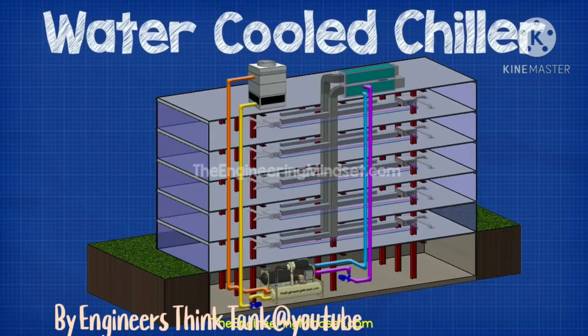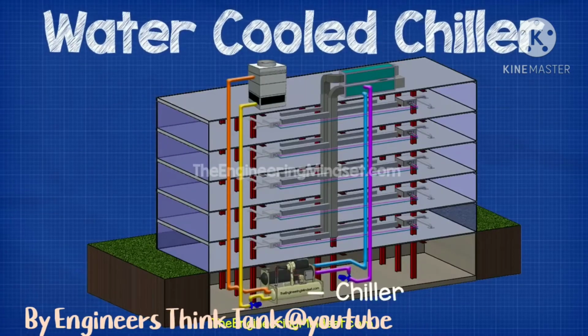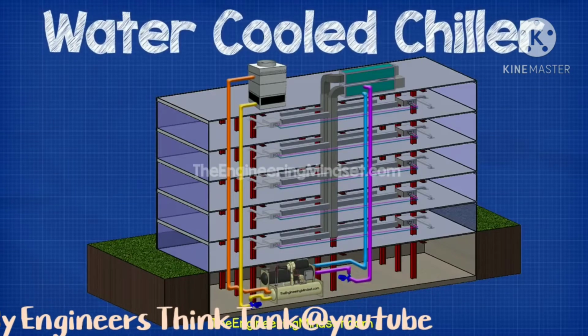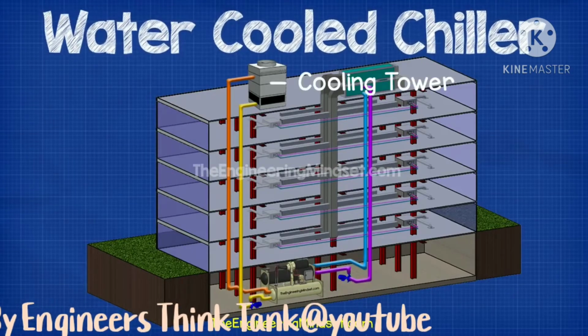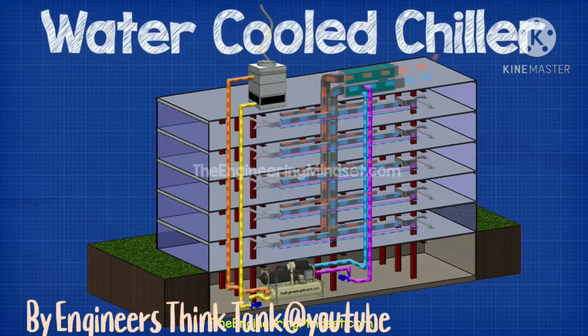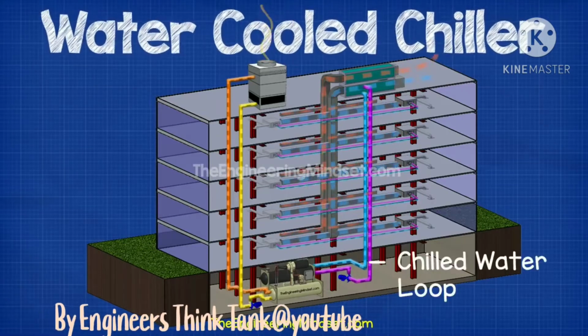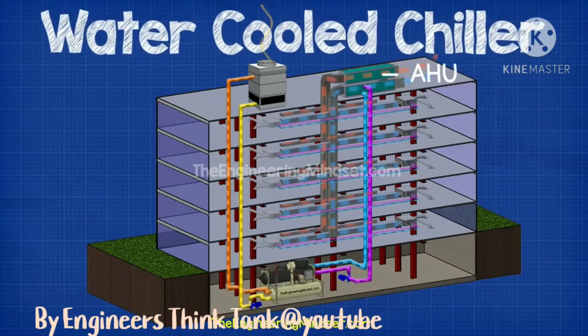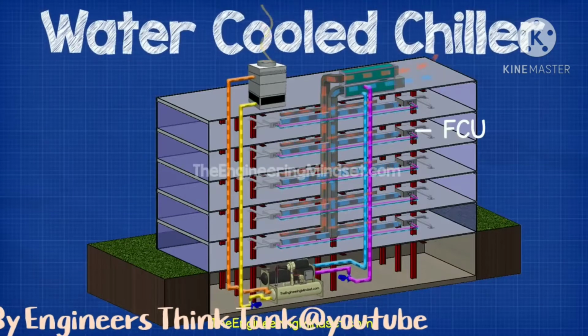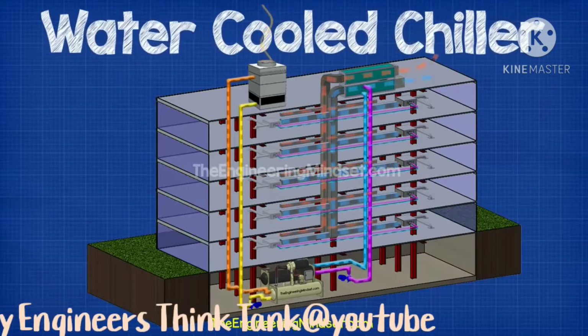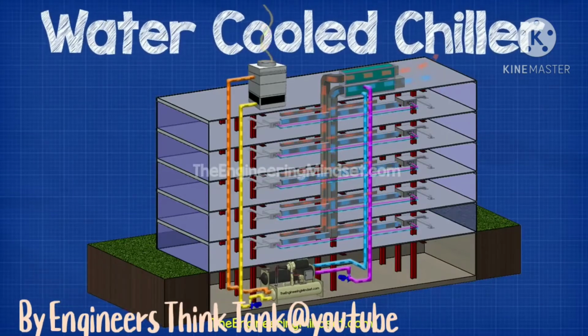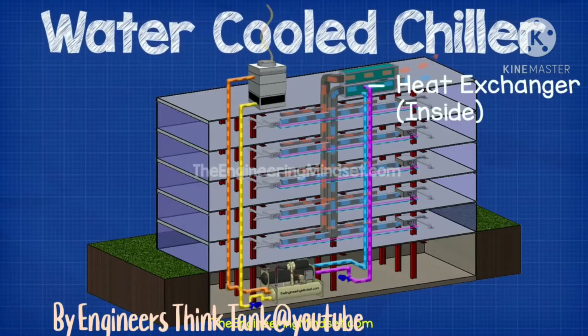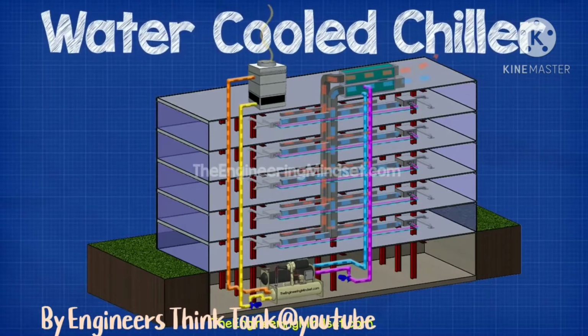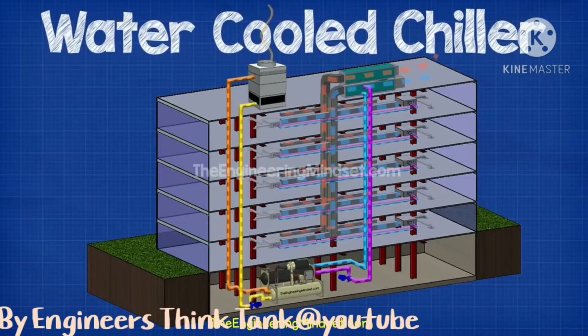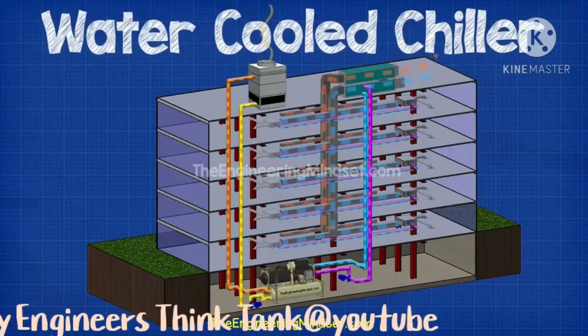Water-cooled chillers are typically located in the basement or the lowest floor of a building. This type of chiller needs a cooling tower to reject the heat from the building. The chiller produces chilled water and pushes this around the building to air handling units and fan coil units. These units circulate the air around the local space as well as the building. The air is then forced across the heat exchangers containing the chilled water, which extracts the unwanted heat before the air is distributed throughout the building.